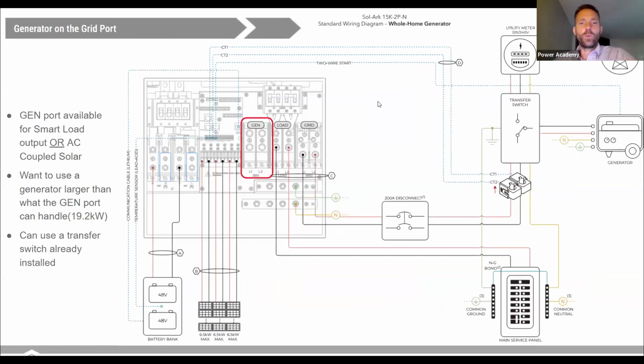So here's that example where I'm showing you a generator connected to the grid port. So the gen port remains open. So if you've got AC coupled solar, you can bring that in through the gen port. Another nice reason you might want to bring the generator in through a transfer switch, you can still use a 2-wire start and you still run off the batteries until the batteries get low, is you could use the gen port as a smart loads port, and you can have up to 80 amps of 240 volt AC on a sub panel that might drop loads off based on battery percentage.